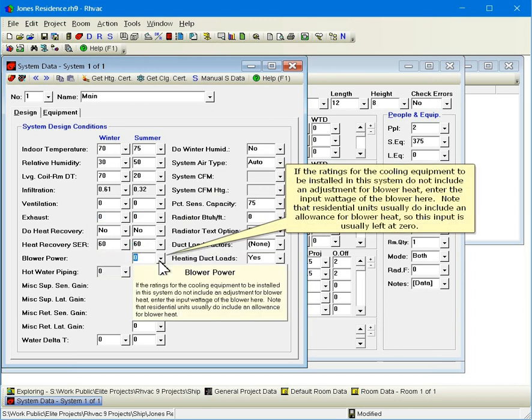If the ratings for the cooling equipment to be installed in this system do not include an adjustment for blower heat, enter the input wattage of the blower here. Note that residential units usually do include an allowance for blower heat, so this input is usually left at zero.